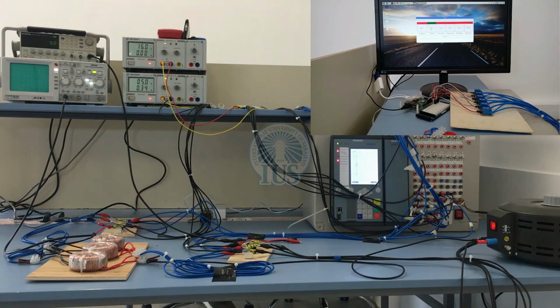Again, the same thing happens for pressure trip. And after that, we have 2 alarms, a temperature alarm and a pressure alarm. They do not trip. They're just like a warning, like, hey, the temperature increased a bit. Someone should go and check it out. So these are those 2. The number 5 is acknowledge. That means that another Siprotec device in the area nearby tripped, because usually Siprotec devices communicate between each other. And that means that our device shouldn't take any action. So when that happens, you can just click and it won't do anything. So this is like an override button. It just disables the entire graphical user interface. You cannot trip or do anything.